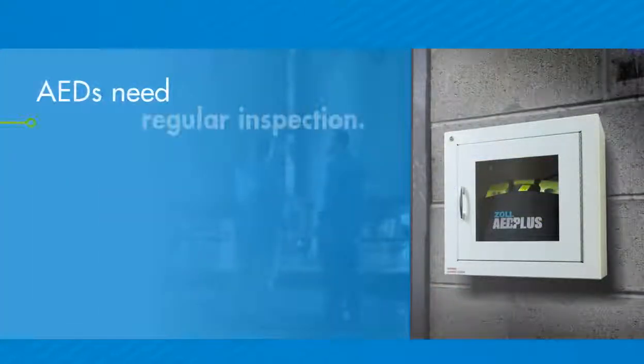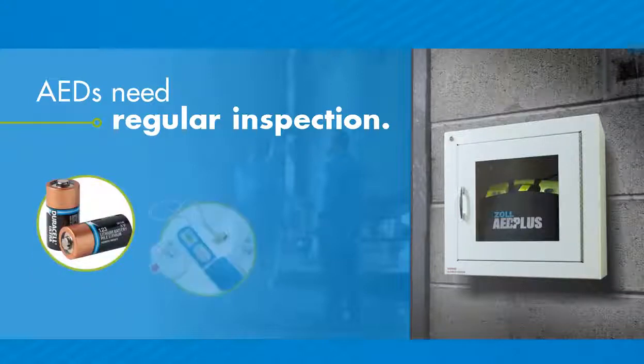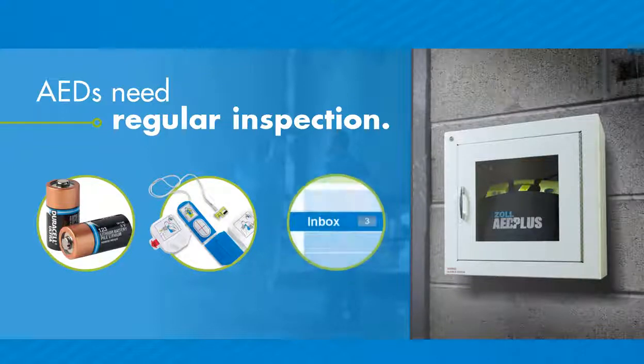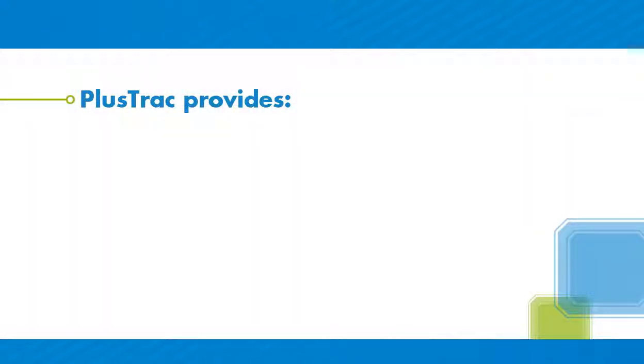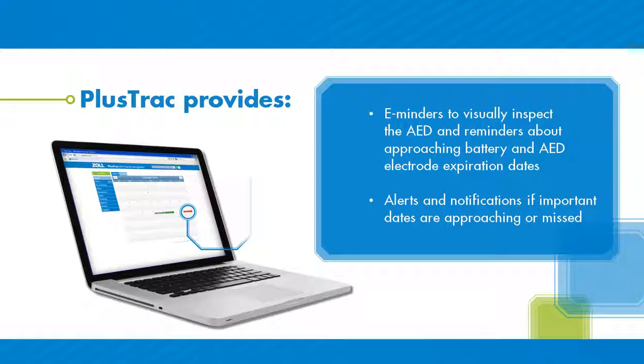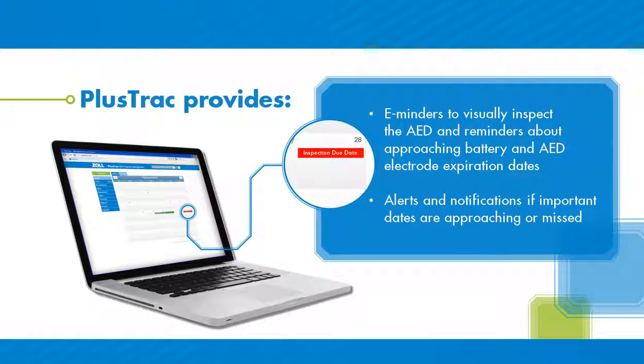AEDs need regular inspection. Batteries and the electrodes used to provide a shock expire over time. Through PlusTrac, the program manager at your site will receive email reminders to make sure everything is in good working order. PlusTrac will help you stay on top of all aspects of maintaining an AED program, including notifying you when consumables are nearing expiration, as well as making sure you're aware of any manufacturer's alerts concerning your AEDs.